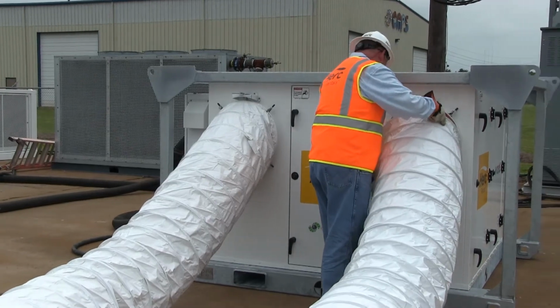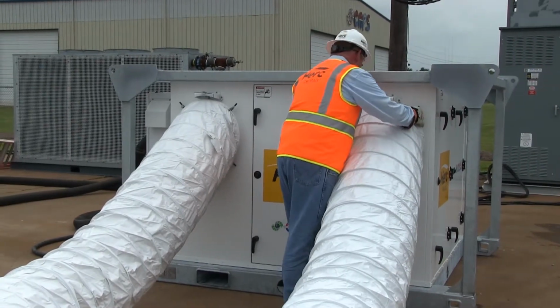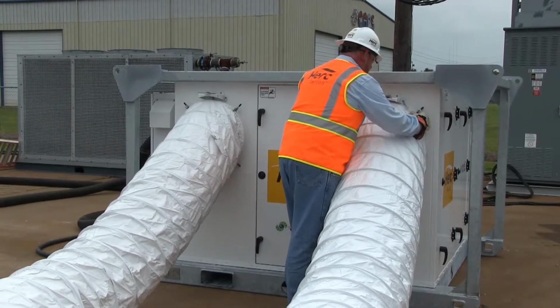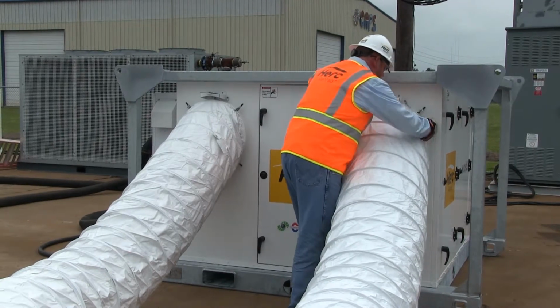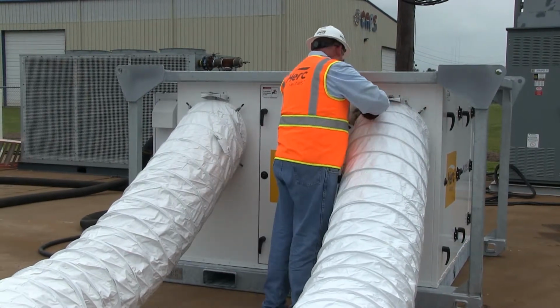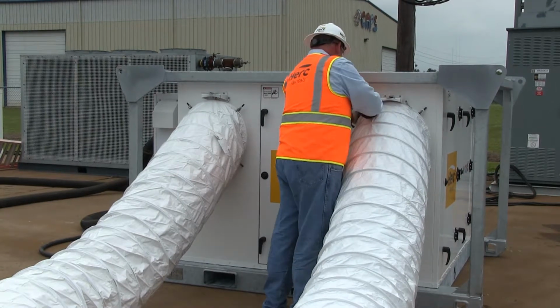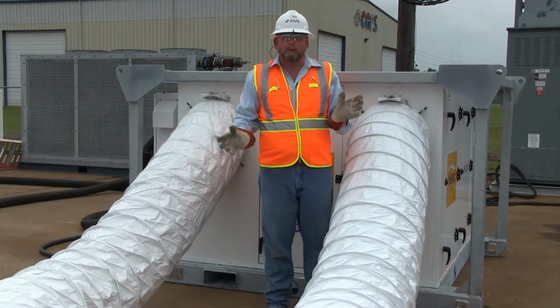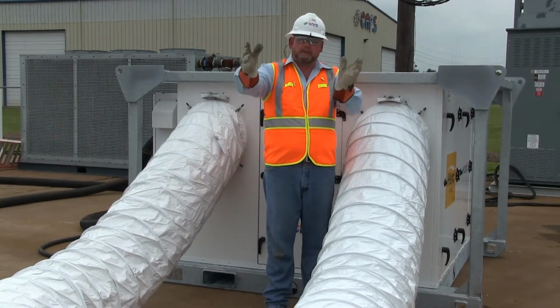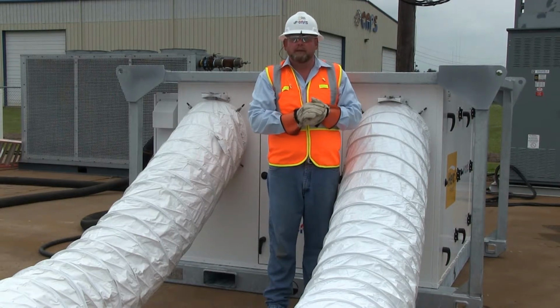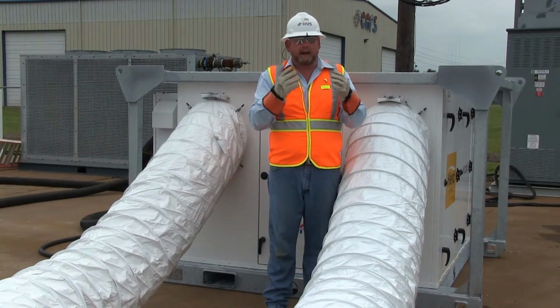And again, I always start at the bottom first and wrap it around to the top. It's a little easier to get the duct ring around the friction clamps. And then we'll lock it in place. And then our duct work is complete. We'll plumb this over into the area that's being served and hook it up to lay flat or into a conditioned space.